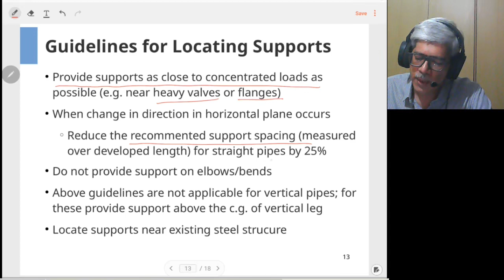In the previous slide, we have seen the span was given for straight pipes. If you are having pipes which are horizontal, but they are having some bend in them, then there is a guideline which says that whatever the recommended support spacing given by the previous table, that needs to be reduced by 25%. So let me explain what it means.